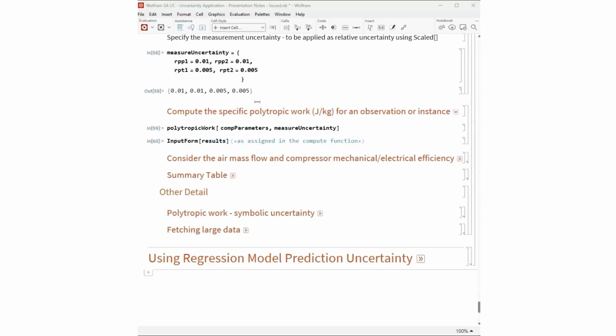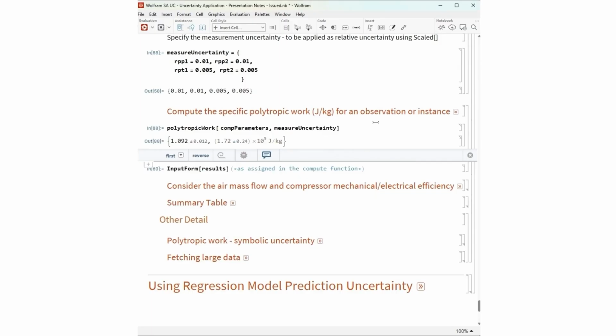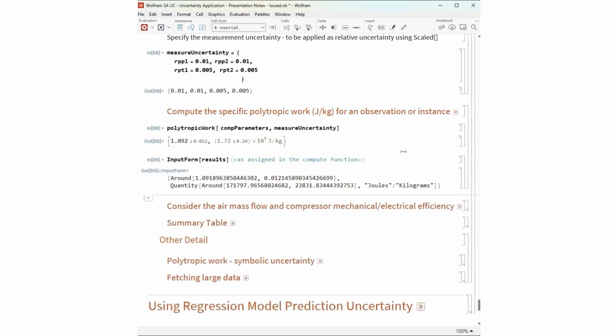Using the above, for one instance observation of pressures and temperatures, you can compute the polytropic index and the specific work with the uncertainties. So using the equation or function defined above, you end up with a polytropic index of 1.092 with its uncertainty, and a work required per kilogram of air of 172 kilojoules per kilogram, with an uncertainty of 0.24. You can also look at the input form of those results, getting the rounded quantities in joules per kilogram.